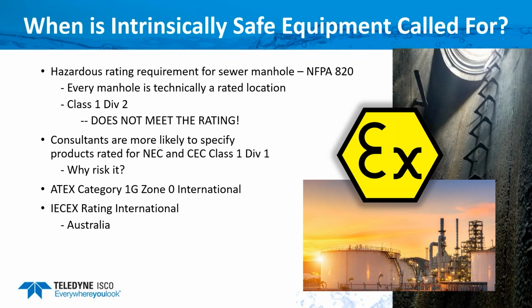Now, the NEC is the National Electrical Code, and CEC is the Canadian Electrical Code, which use class and division to identify hazardous locations. Class 1 refers to flammable gases or vapors that are or may be present in the atmosphere in significant enough quantities to produce a fire or could ignite an explosion. Class 1 is further broken down into two divisions. Division 1 means that it has a high probability of the environment creating an ignitable gas or vapor periodically. Now, Division 2 considers the flammable gases under abnormal conditions. So you should err on the side of caution and expect that hazardous gases are always there. Thus, that's why you need the Class 1 Div 1 specification.